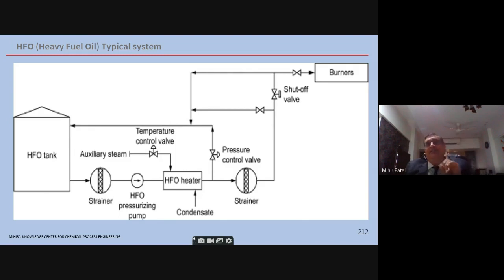So it is always kept pressurized. Normally you keep it around 10 bar pressure. When the burners are operating, they take the draw off from the 10 bar header. You take atomizing steam also to the burners. That atomizing steam is normally 12 bar, and then you have a 2 bar delta there, and then the burners are atomized, and the burners then operate in the fired heater. So this system is very crucial in large plants. It's continuously kept in circulation.